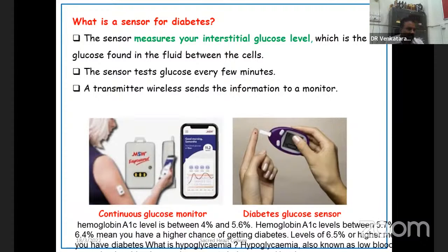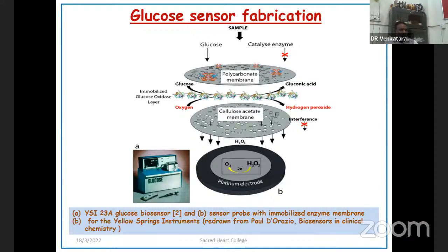Once it is applied, you put a drop of blood on it, and you get a reading. This is an electrochemical measurement, and the technique on which this system works is chronoamperometry. That means we apply a potential and we monitor the current. This current was generated because of the reaction between the glucose and the glucose oxidase, which was attached to the electrode surface. For attaching the glucose oxidase, here is the basic thing: you take membranes, in the polymer membranes, one is cellulose acetate and another is a polycarbonate membrane. Between them we put glucose oxidase.